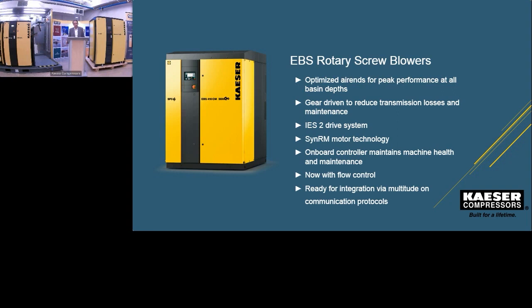Yes, we always talk about VFDs giving you flexibility, but if you look at most machines on the curve, there is a penalty to pay from a performance standpoint as you slow them down. With these screw blowers, that curve is nearly flat, so you can really experience those improvements that we're talking about across the entire range of the unit. So no penalty for ramping it up and ramping it down.